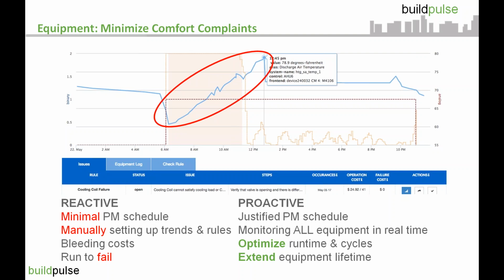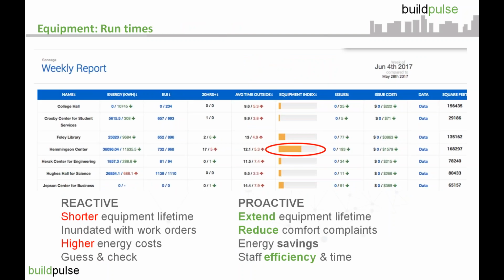Because we found this one night, and every night they're on, we let the client know, and in the short term they changed their startup schedule to match the mechanical cooling to avoid running the system for 3 hours as a recirculating unit. And that's just an example of the kind of things you might be able to find with this.